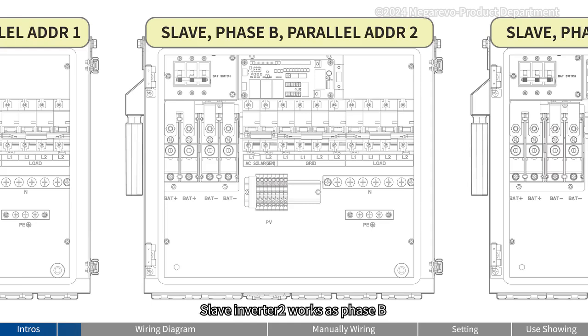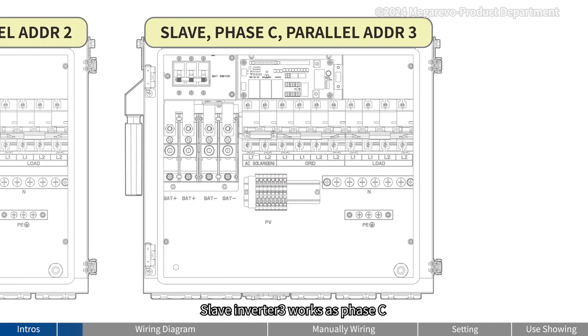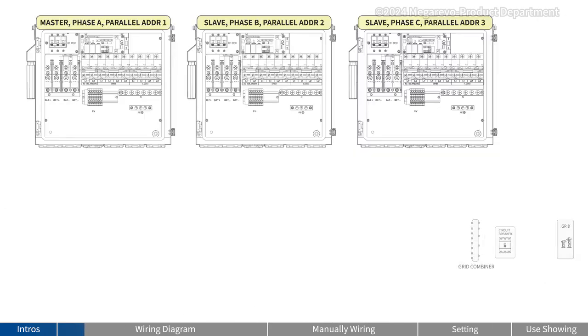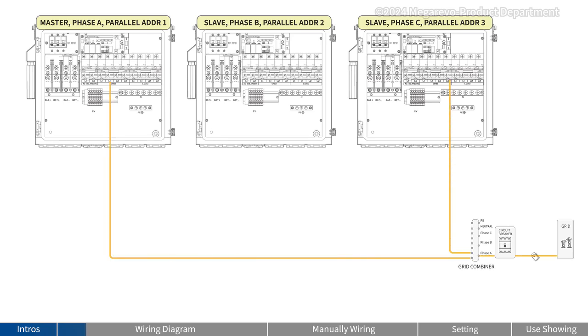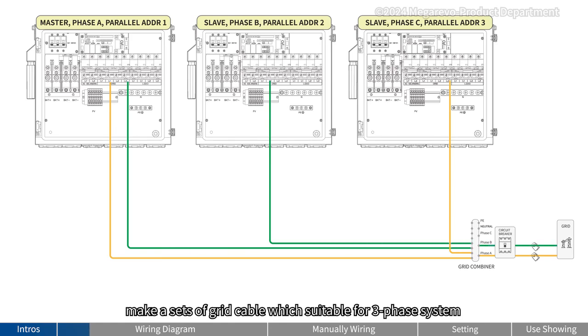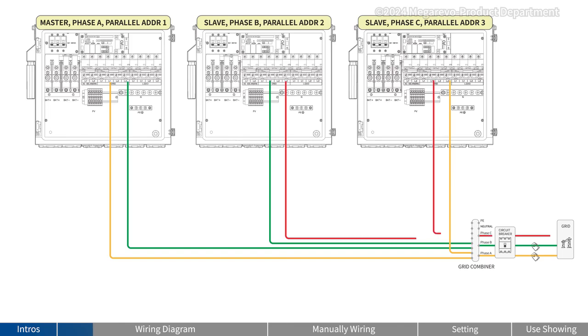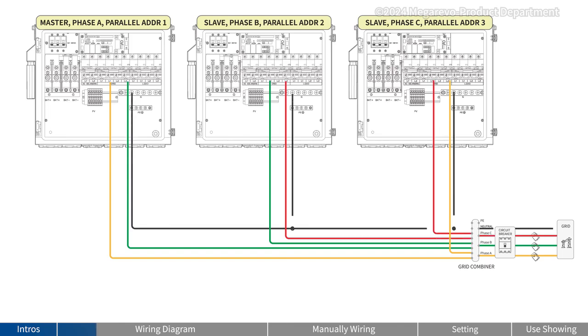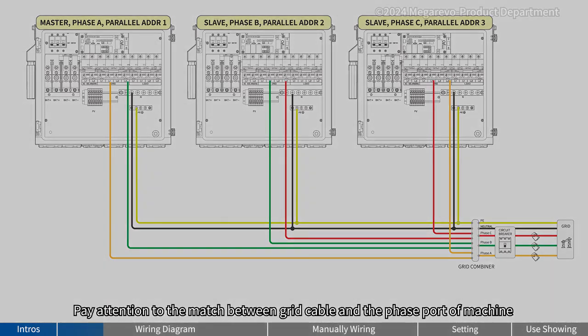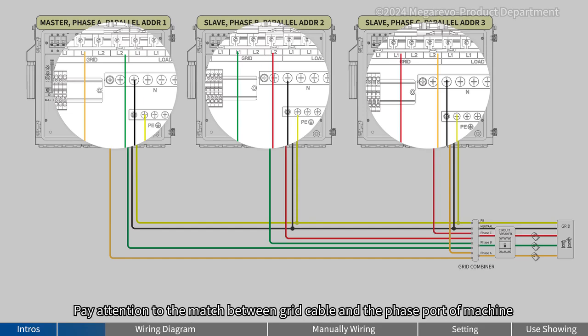Slave inverter 2 works at phase B. Slave inverter 3 works at phase C. We use an AC circuit breaker and a grid combiner to make a set of grid cable which is suitable for 3-phase system. Pay attention to the match between the grid cable and the phase port of the machine.